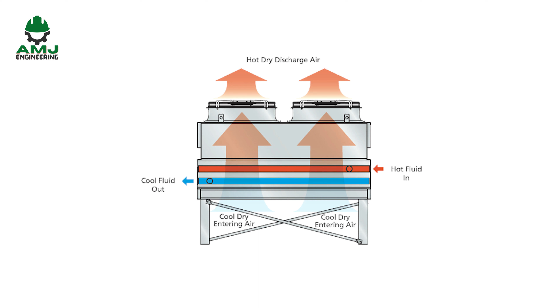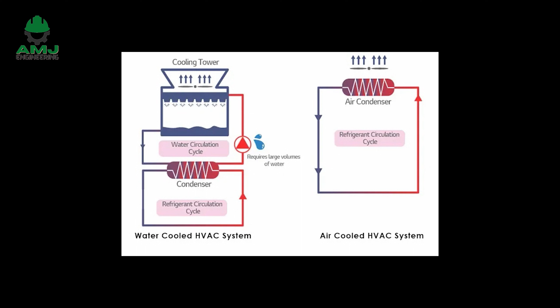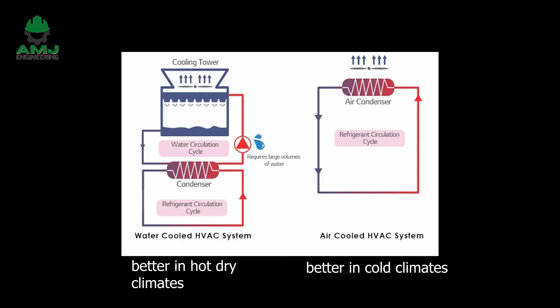Clearly, for a dry cooler to be efficient, the air temperature needs to be cooler than the water or any other glycol solution in the system. This explains why, for example, dry coolers work better in cold climate regions, while wet cooling towers are more efficient in hot and dry climates.